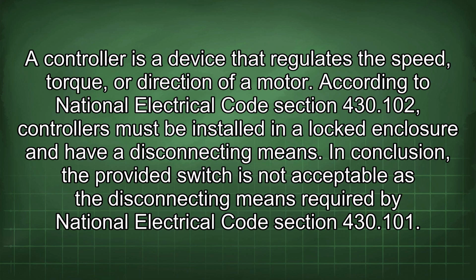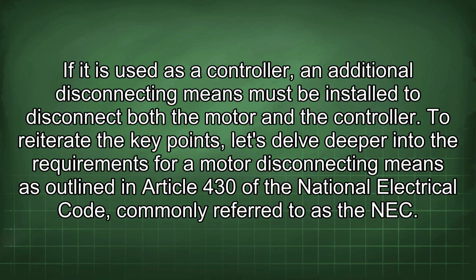According to National Electrical Code Section 430.102, controllers must be installed in a locked enclosure and have a disconnecting means. In conclusion, the provided switch is not acceptable as the disconnecting means required by National Electrical Code Section 430.101. If it is used as a controller, an additional disconnecting means must be installed to disconnect both the motor and the controller.